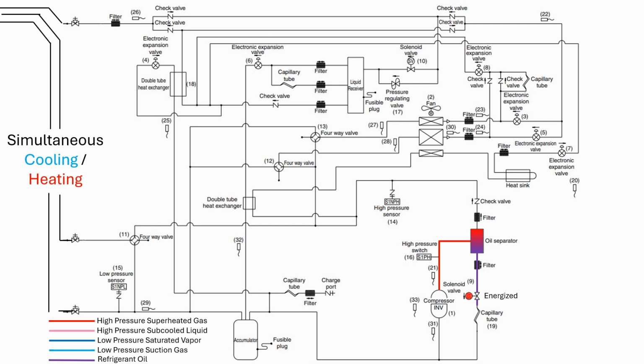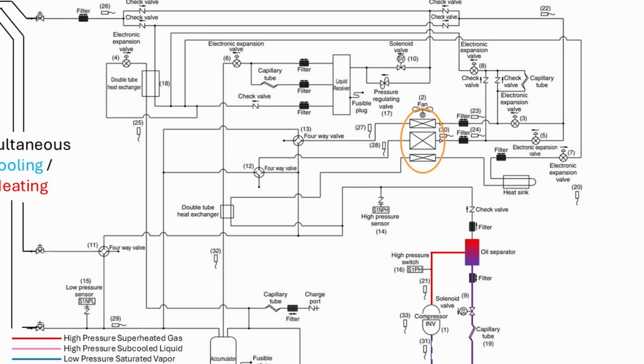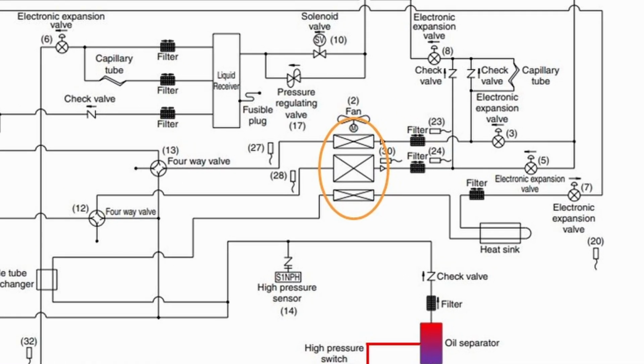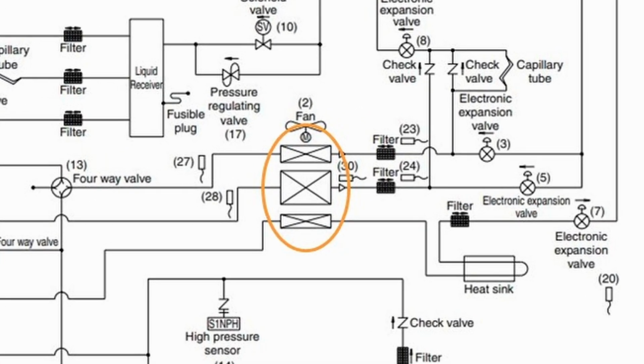The oil passes through the solenoid valve, then through a capillary tube to remove any liquid refrigerant that may be trapped in the oil, and then returns the oil back to the compressor where it belongs. Notice that the outdoor unit heat exchanger is divided into 3 separate compartments, each a different size, to more accurately control the amount of subcooling or superheat needed by the system.